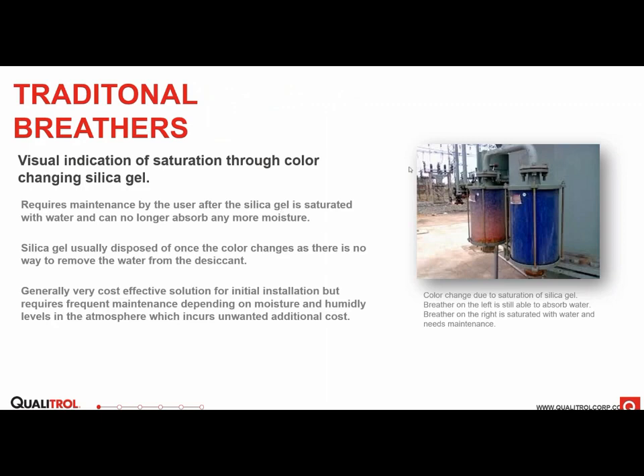As we mentioned, traditional breathers operate on the basis of visual indication to know when the silica gel needs to be replaced or taken out and heated manually to regenerate it. It's strictly based on color changing. There's no data, no sensors. We sometimes joke around and call them a dumb breather. These are generally a very cost-effective solution for the initial installation, but over time it requires constant maintenance every 6 months or a year to change the silica. And sometimes it's difficult to know when the silica is completely saturated.